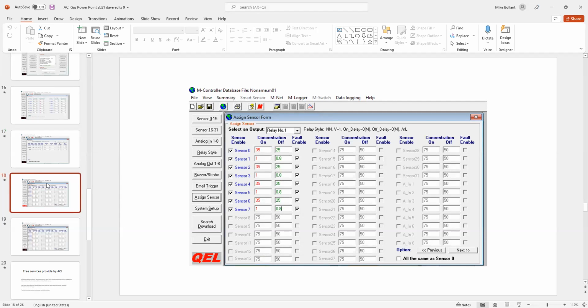So then the next step, we're going to assign the sensors to the relays. So we choose relay 1 up top. That's going to be your low level alarm. In this case, we're doing 35 parts per million to turn on CO and 1 part per million for NO2. And our off limit is going to be 25 and 0.8. And that's going to be our first alarm level. And we're assigning that to relay 1. So it doesn't matter if either the CO or the NO2 reaches those trip levels, it's going to turn relay 1 on.